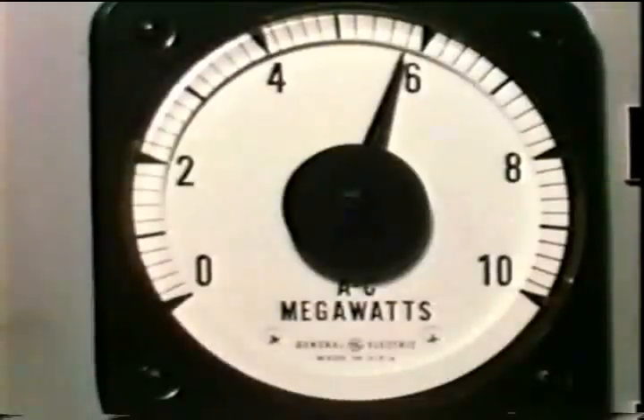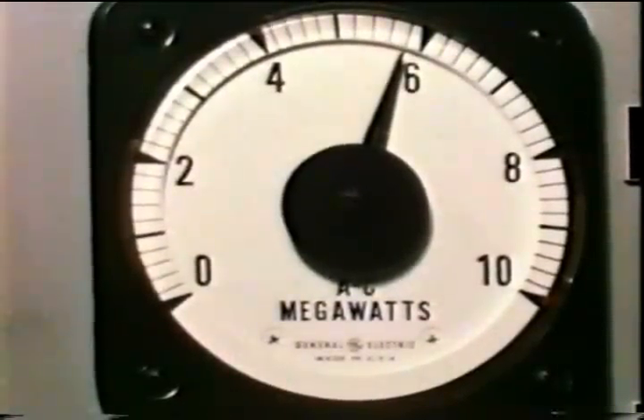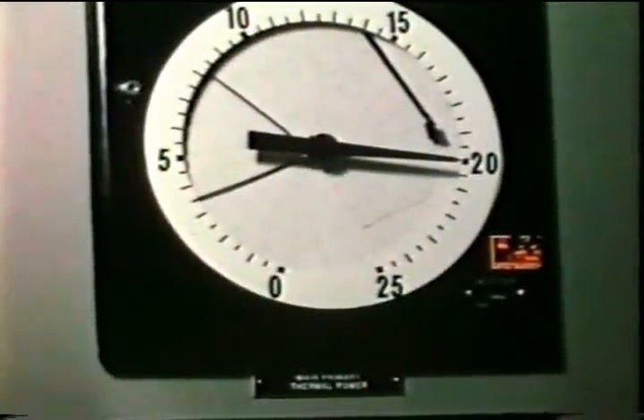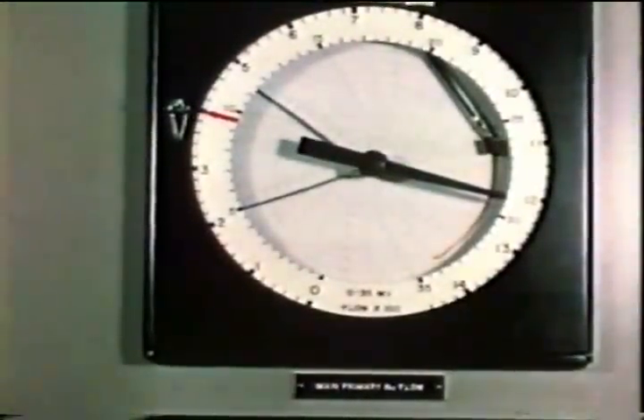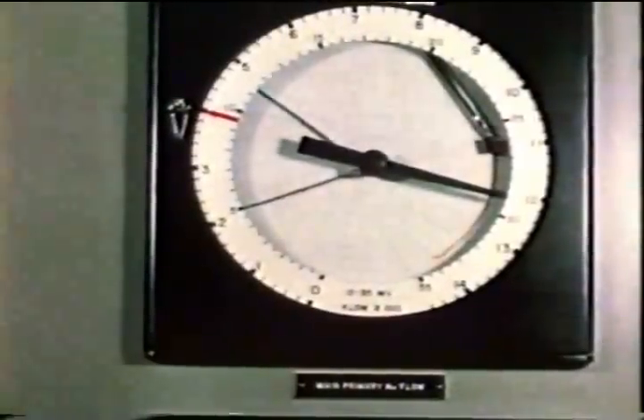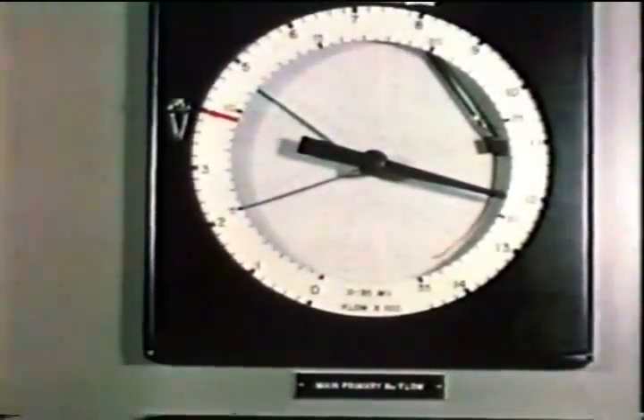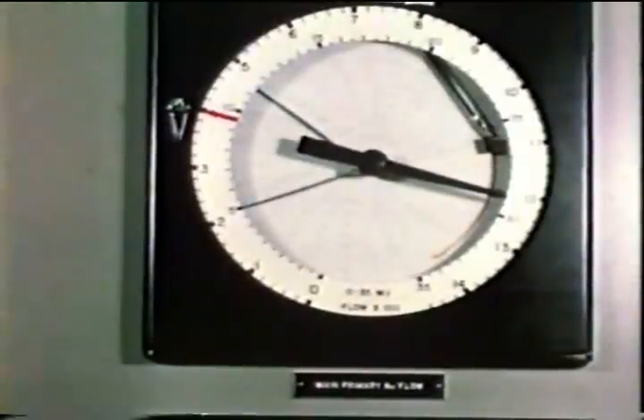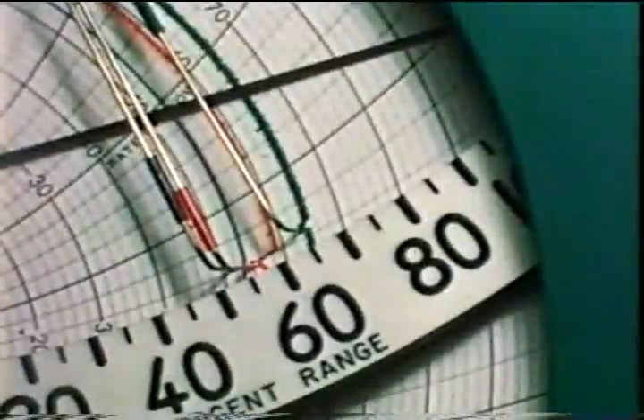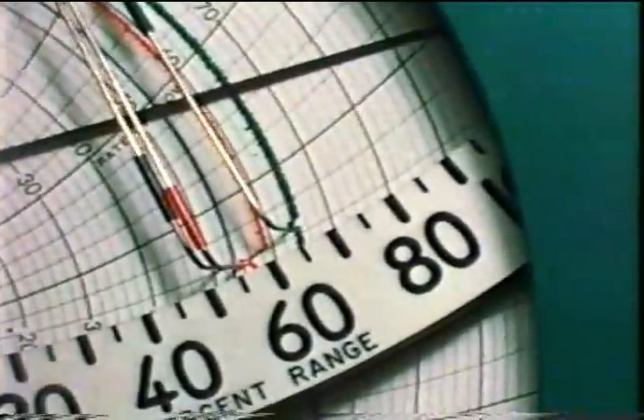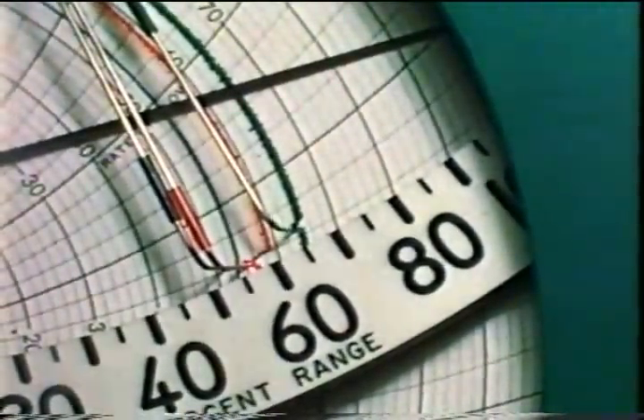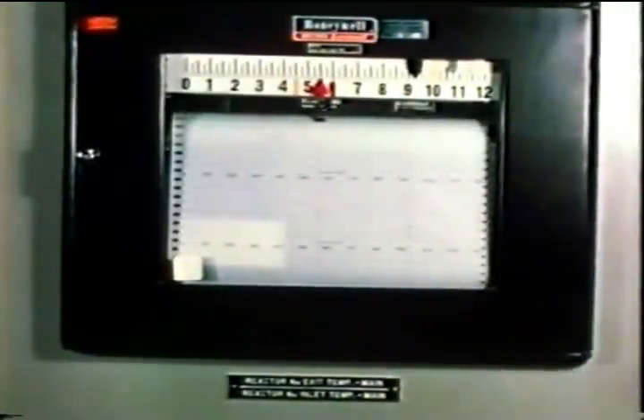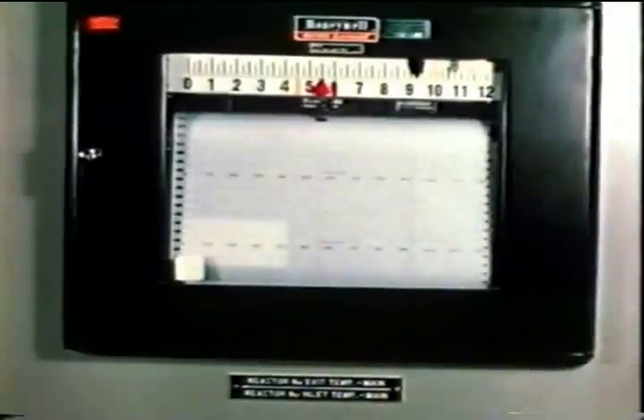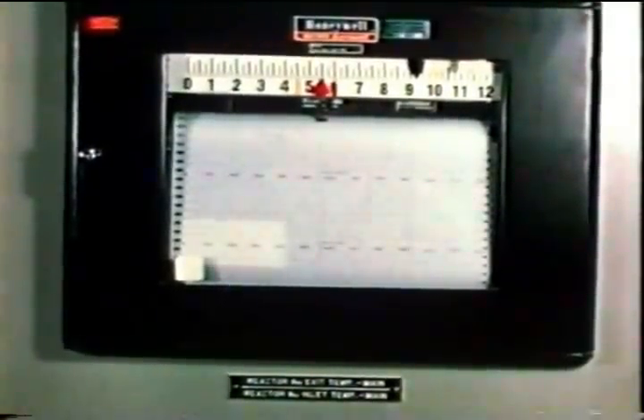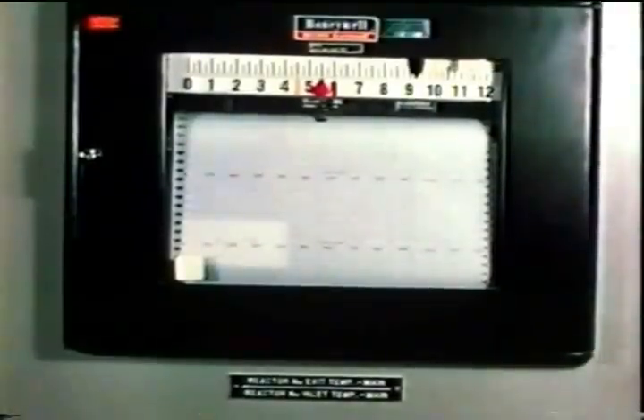Electrical power reached 5.8 megawatts. Thermal power, 20 megawatts. Main primary sodium flow rate, 1,200 gallons per minute. Main secondary sodium flow rate, 1,200 gallons per minute. Steam flow rate, 54,000 pounds per hour. Reactor inlet temperature, 560 degrees Fahrenheit. Reactor outlet temperature, 925 degrees.